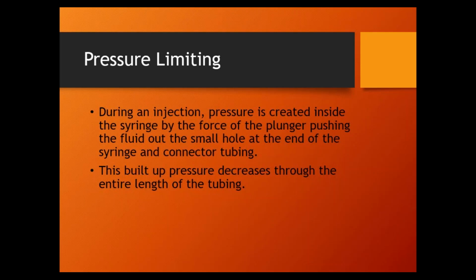Now, okay, so then why is the catheter rated at 1,000 PSI, for instance? Is it ever possible that I could get 1,000 PSI to the catheter or to the needle? Yes. As long as we have flow through the needle or through the catheter, everything I said is true: very, very high pressure here, very, very low pressure right now. But if there's an occlusion somewhere down the line, if the catheter is clogged, or the connective tubing is occluded or pinched, then the pressure here is equal to the pressure everywhere up to the point of the occlusion.